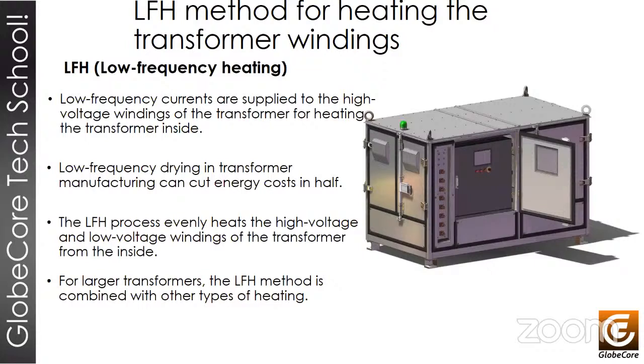And now for my favorite part, low-frequency heating. Low-frequency heating is quite a unique process for drying the transformer insulation by injecting a regulated low-frequency current into its high-voltage windings. This system works better and faster than traditional methods. It can reduce energy costs by up to 2 times and greatly speeds up the operating process.